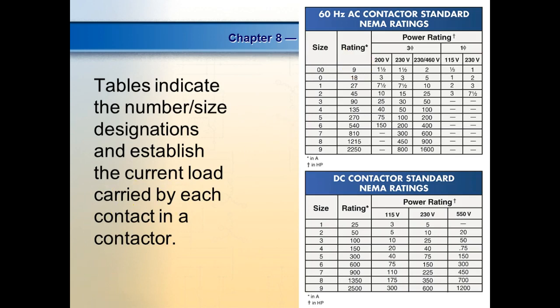So the only difference between a contactor and a motor starter is motor starters are going to have an extra assembly added to them called overloads, right? And the overloads are usually actually separate, but they'll mount them on the same mounting panel. Another thing that we need to look at is the size of these contactors.